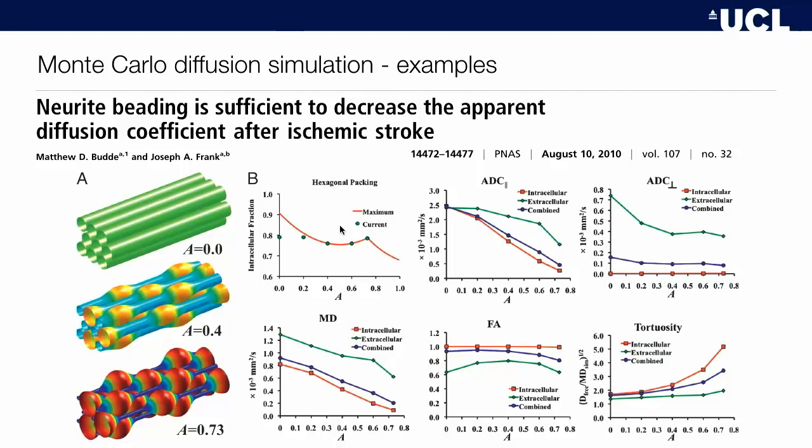This is a very good example where numerical phantoms can be useful, where it's perhaps difficult to modulate these things in physical phantoms. Here we can at least test in a very simple case by manipulating the amount of beading in the phantom to see whether we see the desired effect. If there's no effect in the phantom, chances are this is not likely to be a major contributor in the real world. Okay.